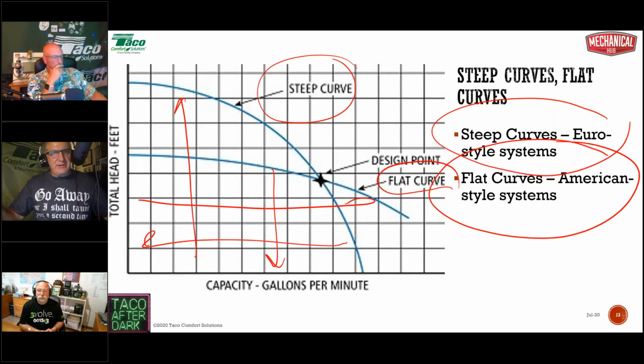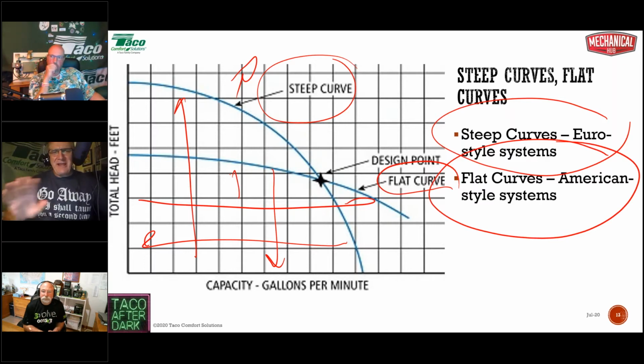It's designed to a 40-degree delta T, keep the flow down, even at low flow rates. With the really small pipe, you're going to have high head. So steep curves and flat curves were basically, what I say, necessity is the mother of invention. These curves were developed because they were necessary for those types of systems. So I hope that helps a little bit. Why we have steep curve pumps, why we have flat curve pumps.